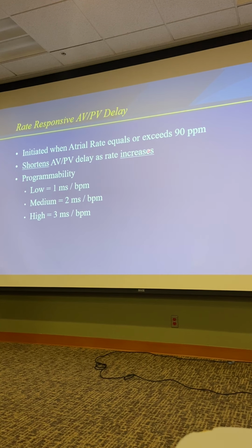This is rate response. With rate response for the AV delay, we'll shorten that AV delay as the heart rate goes up to mimic normal physiology. And this is just an example of how it's done. When the heart rate gets up to 90, the device will be told to add or subtract a certain number of milliseconds from the programmed AV delay. And we can change that. What you'll typically see on the floor is programmed to low, medium, or high. A young active person, we want it high. As soon as you get active, we want it to change. An old, frail person, we might want it to be much more gentle.